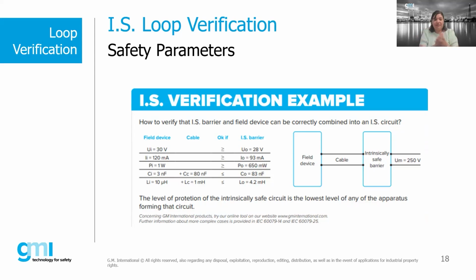So that's pretty much the logic here. It's basic math that you have to do to compare voltage, current, and power for the field device and the IS barrier. And then the cable in between is also part of the system. For that, you have to do the capacitance and inductance calculation, knowing the length of the cable you're going to have. Or you can do the math to see what's the maximum amount of feet or meters that you can have in that system.